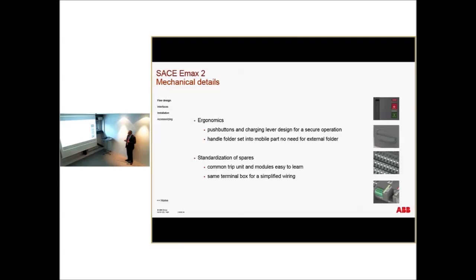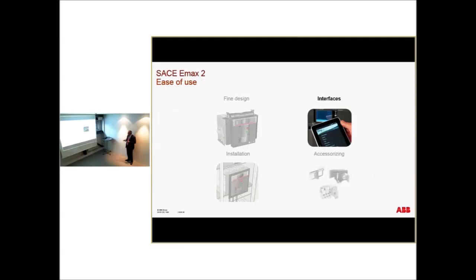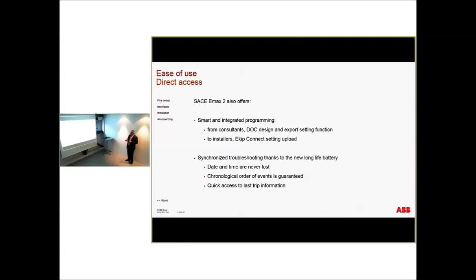The IP protection is the maximum available. This also is fully protected. And electronically, it is easy to use. Also, when we make a discrimination study, you need to download everything in a format or in a device, and then download it inside the breaker. So you need to do two operations. In this case, with the new one, the software that makes the discrimination lets you put exactly the discrimination inside the breaker. So there's no need for more work on that.